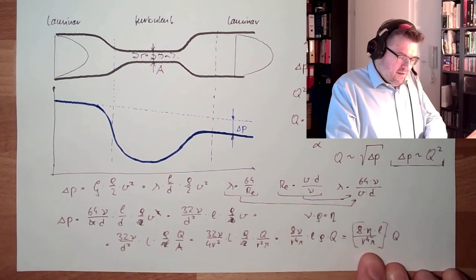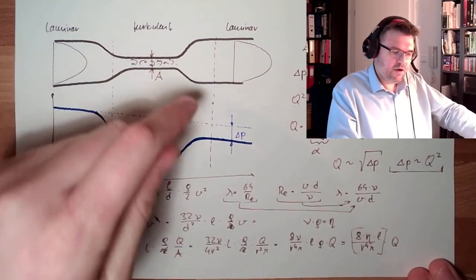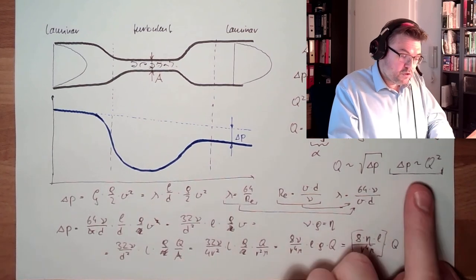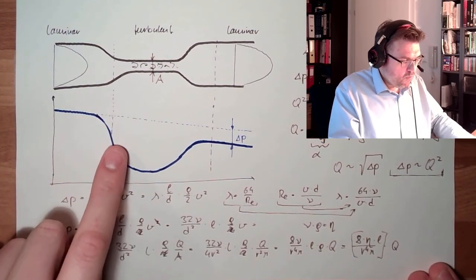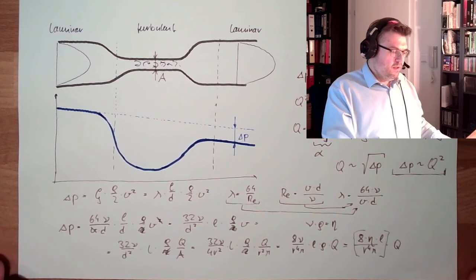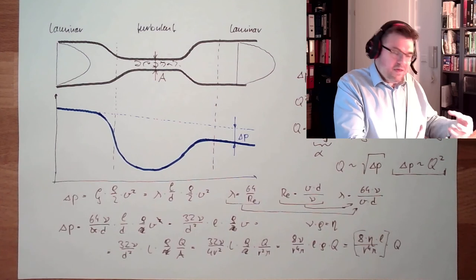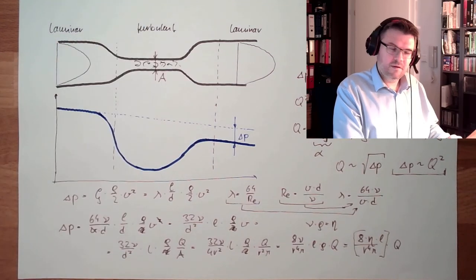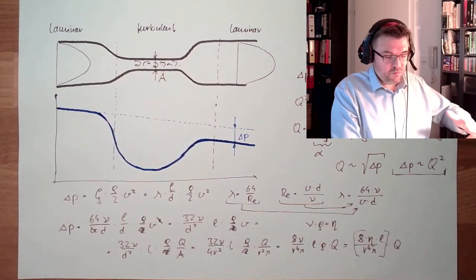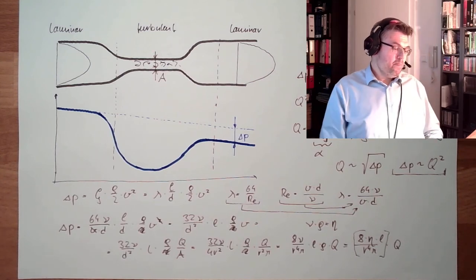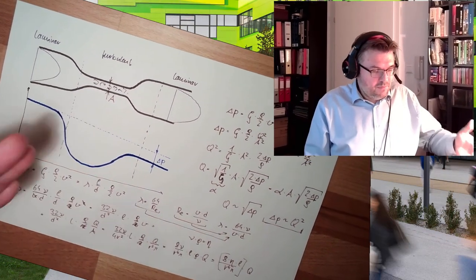Think about this — you can re-watch the video. In the laminar case there is a proportional factor: we drop proportionally to the flow. Here in the turbulent region we drop proportionally to the flow squared — so we drop more. And this is exactly the remaining pressure loss that happens at a narrow position in the tube. The throttle point gets hot, and there is a certain pressure loss at this orifice, nozzle, or throttle point — however you want to call it.